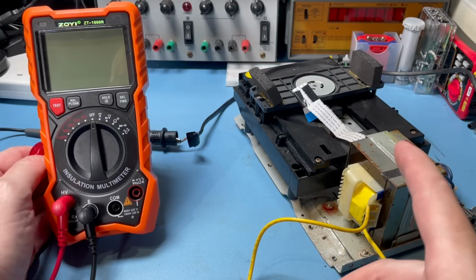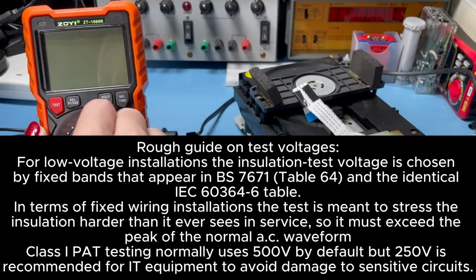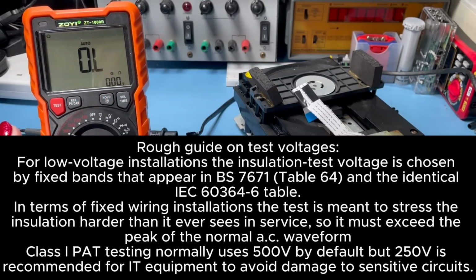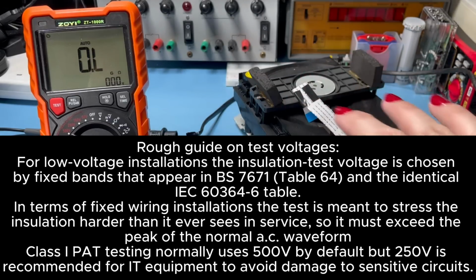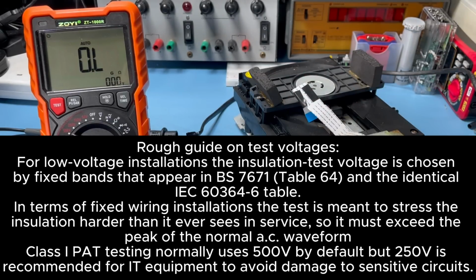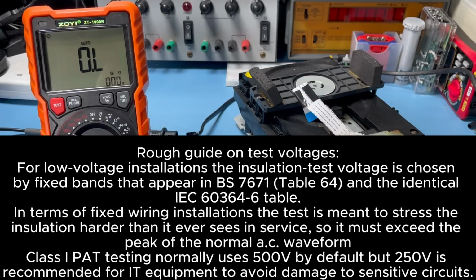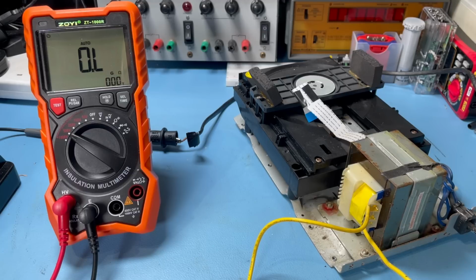Now it's a 250 volt rated product, so we can easily test this at 500 volts, because we're only testing the transformer in this case. If it was something with sensitive electronics inside, I might be more inclined to test it at 250 volts, but this is fine at 500. So we're going to do a couple of different tests here.